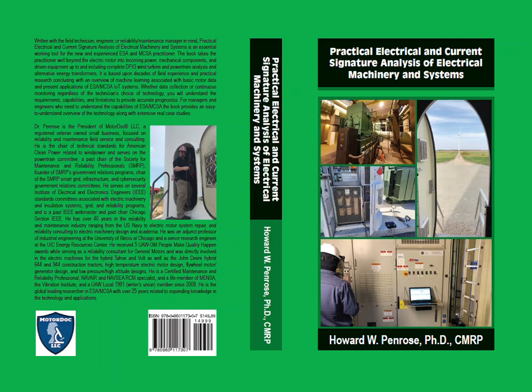During this time, I began performing a little research into ESA/MCSA and noted the relationship between vibration analysis and current signatures. I convinced the sales manager and shop manager to set up a meeting with the customer's management and technicians with the requirement that we could take a look at the data that they were using to make conclusions. As it turned out, they were using a different number for the number of rotor bars than we provided because their data on the motor showed a different set of peaks and there was no pole pass frequency in the motor, so they concluded that the fault was dynamic eccentricity, probably caused by smeared laminations.